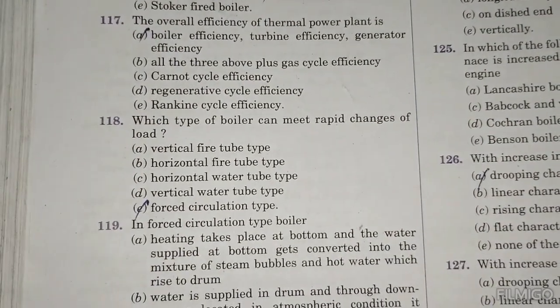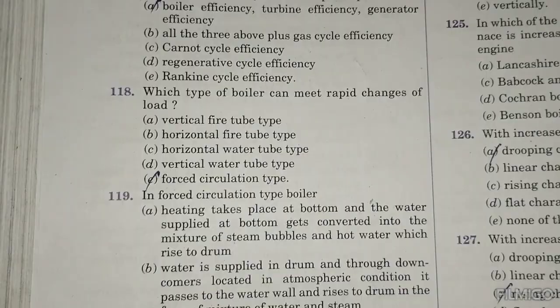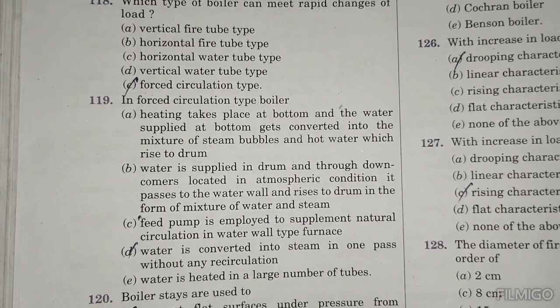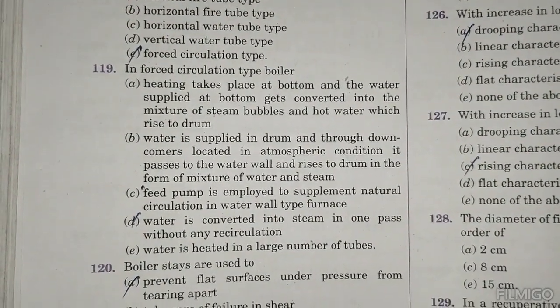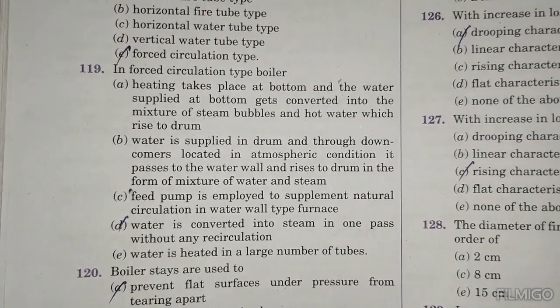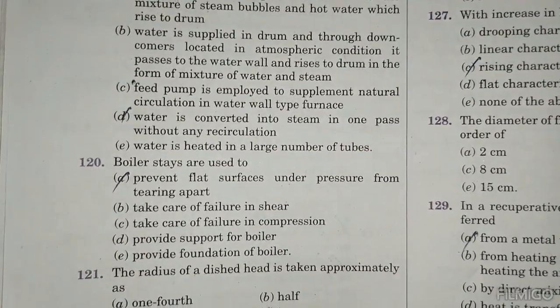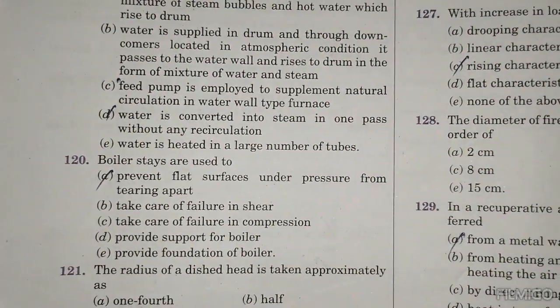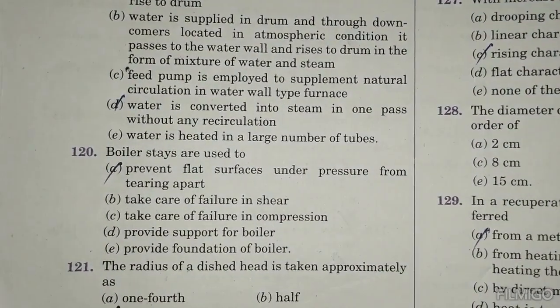Which type of boiler can meet rapid change of load? Forced circulation type. In a forced circulation type boiler, water is converted into steam in one pass without any recirculation. Boiler stays are used to prevent flat surfaces under pressure from tearing apart.